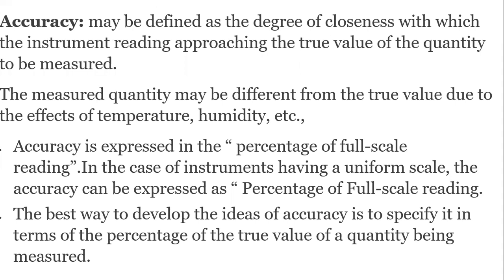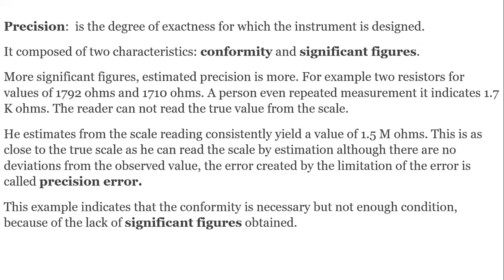Accuracy is defined as the degree of closeness with which the instrument reading approaches the true value of the quantity being measured. The measured quantity may differ from the true value due to effects of temperature, humidity, etc. Accuracy is expressed as a percentage of full scale deflection or as a percentage of true value. When expressed as percentage of full scale deflection, it is advisable to use the instrument at its highest range.